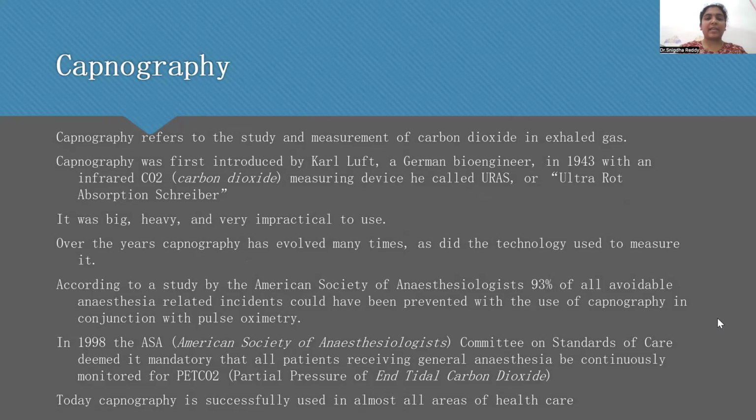According to a study by ASA, 93% of all avoidable anesthesia-related incidents would have been prevented if capnography was used with pulse oximetry. In 1998, the ASA Committee on Standards of Care deemed it mandatory that patients receiving general anesthesia be continuously monitored using ETCO2. Nowadays, capnography is used successfully in almost all areas of healthcare, from operation theater to ICU.